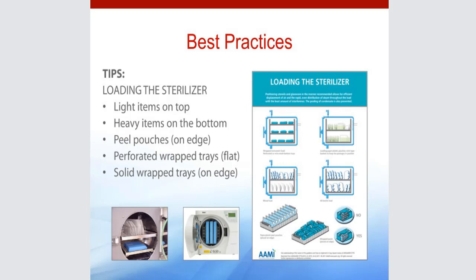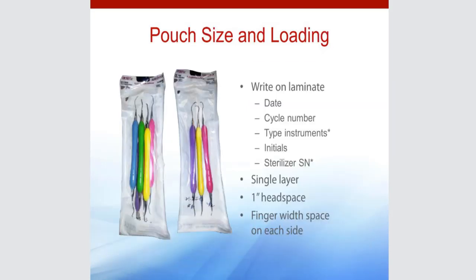If you are using cassettes and pouches and you want to put a cassette in horizontally, that cassette has to be by itself. You cannot stack a smaller cassette on top of it, nor can you put instrument pouches on top of a wrapped cassette. Again, best practice would be like you would see on that middle picture, turning it up on edge and loading them vertically, and you'll see again space in between. You don't want to pack them tight like books on a shelf.